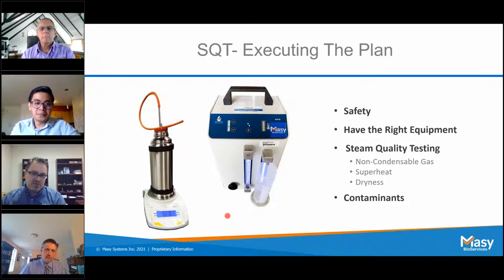The non-condensable gases will collect in that tube there that's in the center of the device. And then you will have a graduated cylinder on the right-hand side, which will collect the water that comes out. And we compare those two measurements to see where the non-condensable gases are at. So that describes the equipment.